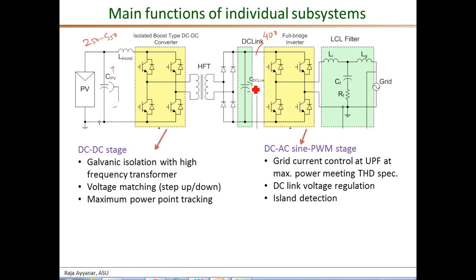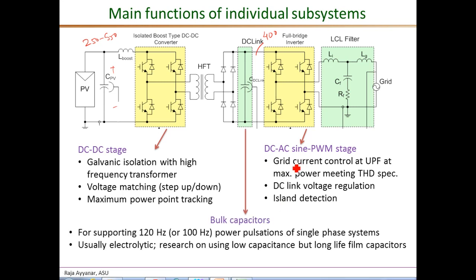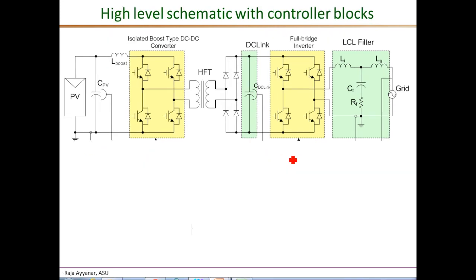The boost stage draws the maximum possible power from the PV and dumps it into the DC link, and the DC-AC stage, by regulating the DC link voltage to the set value, injects the correct power into the grid. The DC-AC stage is also responsible for the anti-islanding control loop. The role of the bulk capacitors is to balance the difference between the pulsating power at the grid output and the continuous DC power drawn from the PV. This balance is supported by the DC link capacitor, which is currently a large electrolytic capacitor array, though research is ongoing to use low-capacitance, long-life film capacitors.